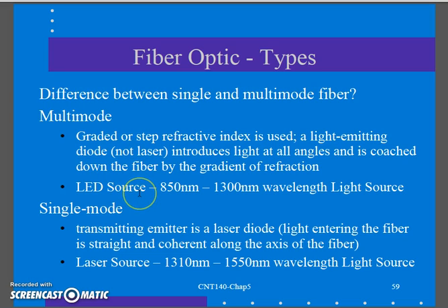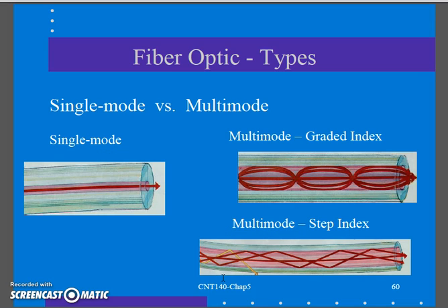Meanwhile, Singlemode, I'm using a laser light source, a single ray of light down the core of the fiber, and my light sources are usually in the 1310 nanometers up to 1550 nanometers. Longer wavelengths to go longer distances.